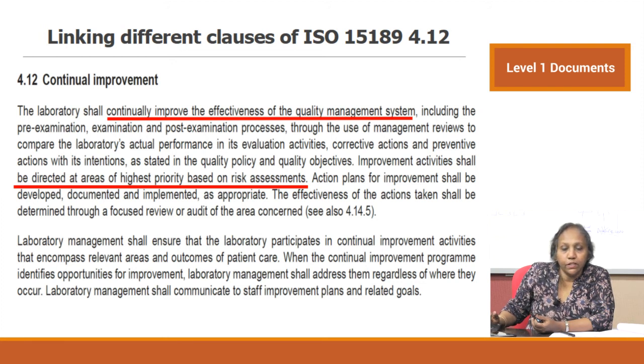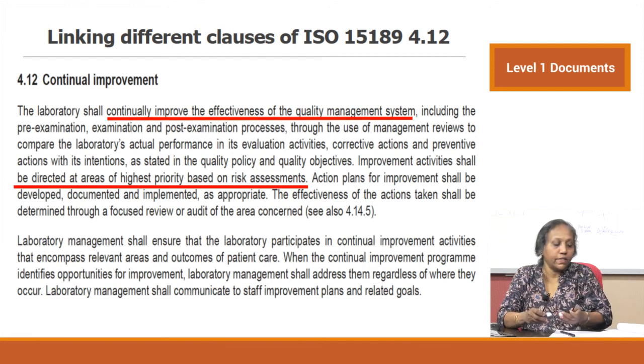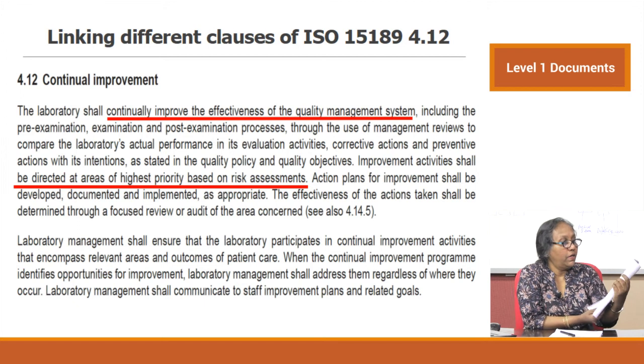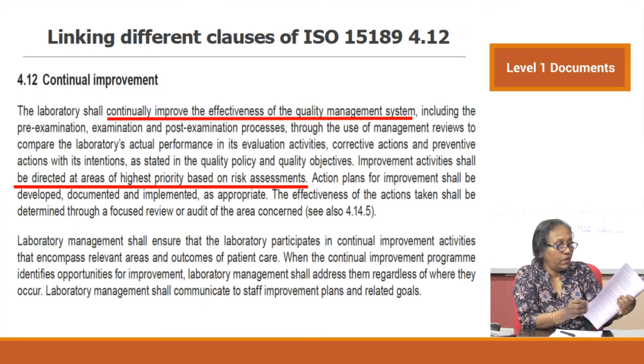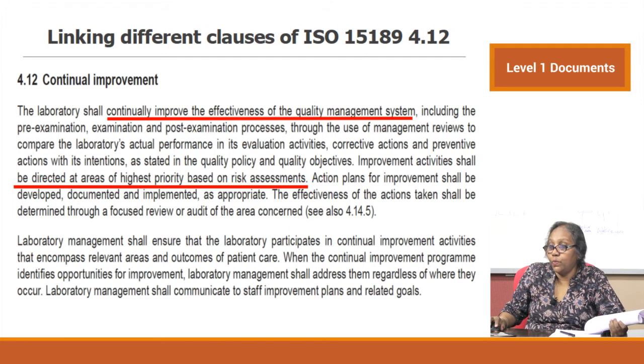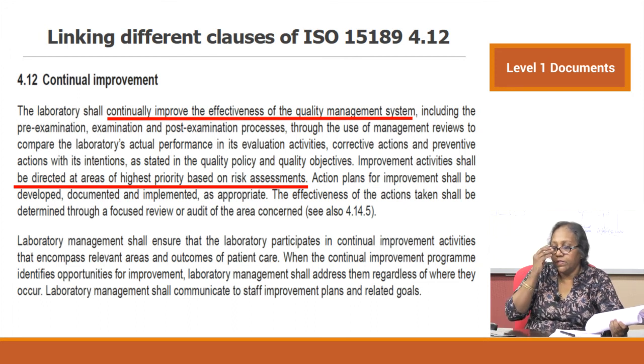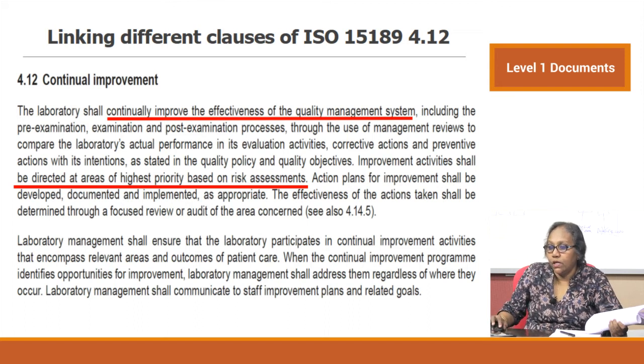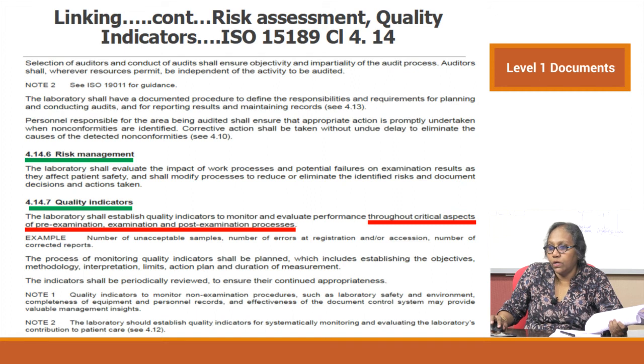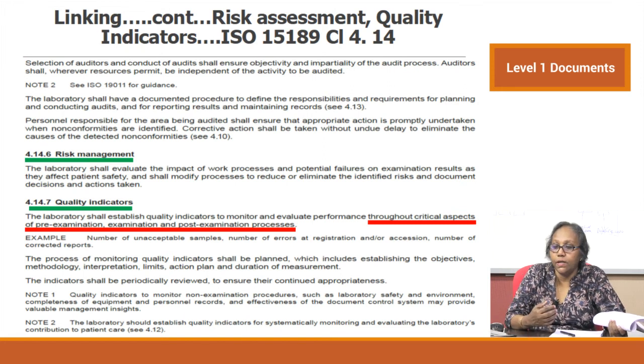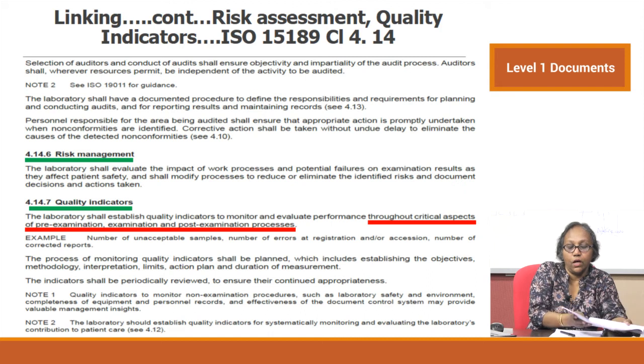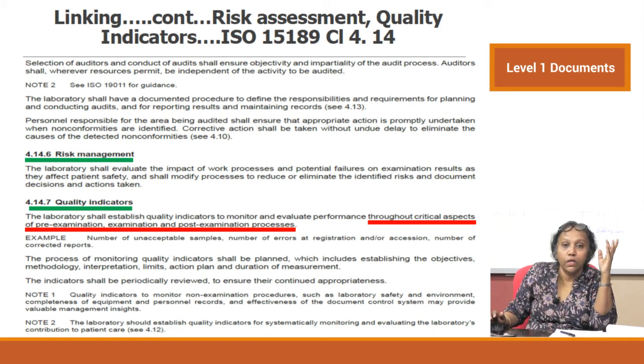Quality objectives appear in the standard at clause 4.1.2.4 — already discussed. At clause 4.12, the standard talks about continual improvement: the laboratory shall continually improve the effectiveness of the QMS, directed at areas of highest priority based on risk assessment. Clause 4.14 again discusses risk management and quality indicators. There are multiple areas of the standard addressing continual improvement, which is why the objectives and indicators in the pyramid were shown misaligned to the right.